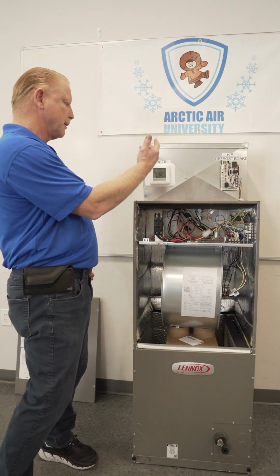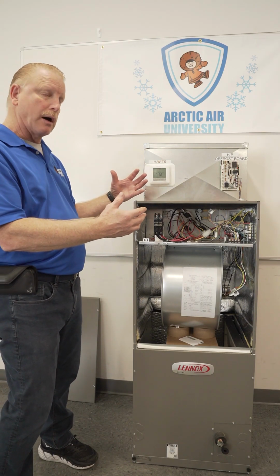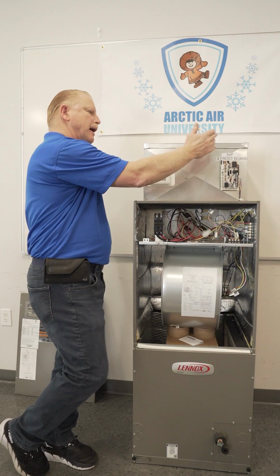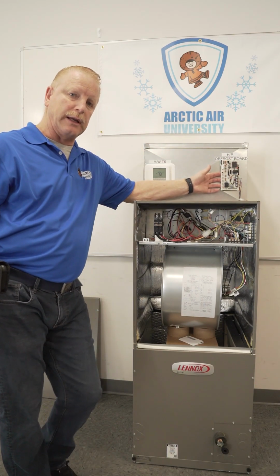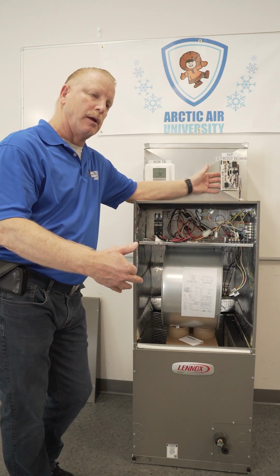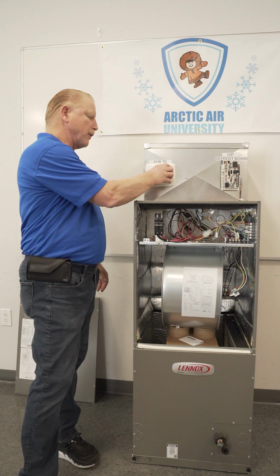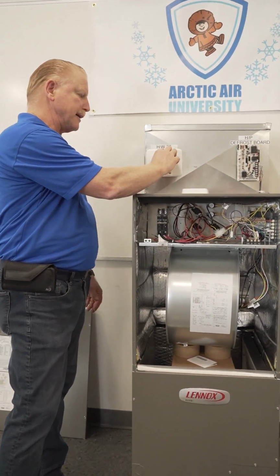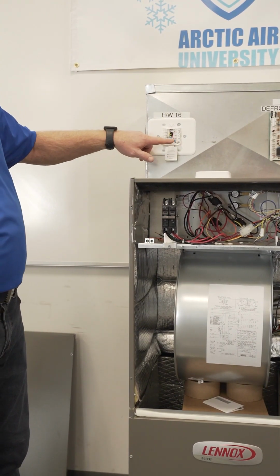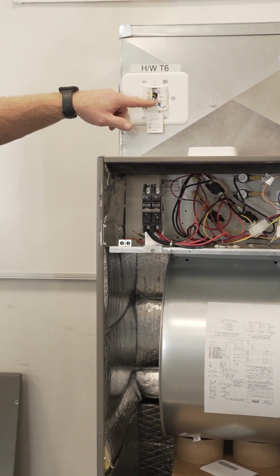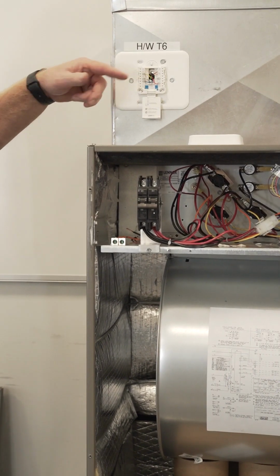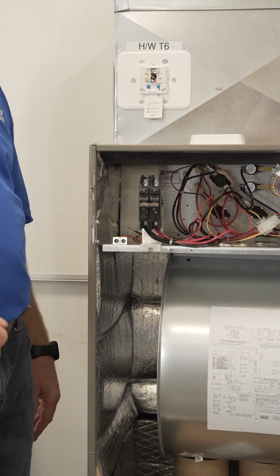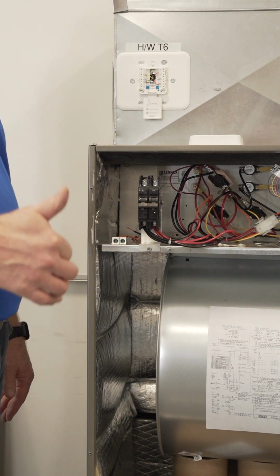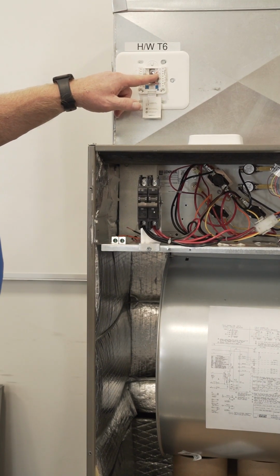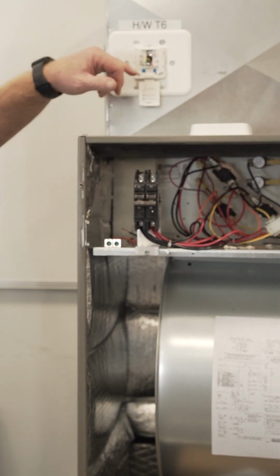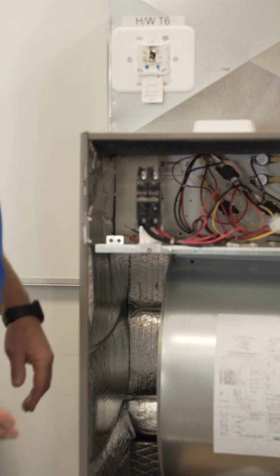Our next step is our thermostat wiring. Once you get all your thermostat wire run, you're gonna get it up to your thermostat and to your outdoor heat pump. I'm just showing the board here to make things easier, but obviously this is gonna be outside in the heat pump. As far as wiring goes, we're using, again, a Honeywell T6. Basically here, you've got your R and common, 24 volts, G for your fan, Y for your compressor. On a heat pump, the compressor is always energized and always running for both heating and cooling. Remember that, all right? We also have auxiliary heat on here that attaches to our strip heaters to bring auxiliary heat on, and the O/B terminal.